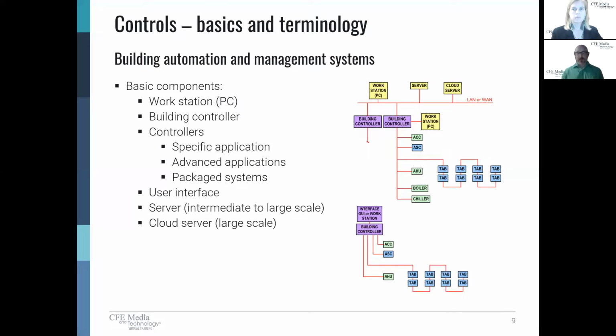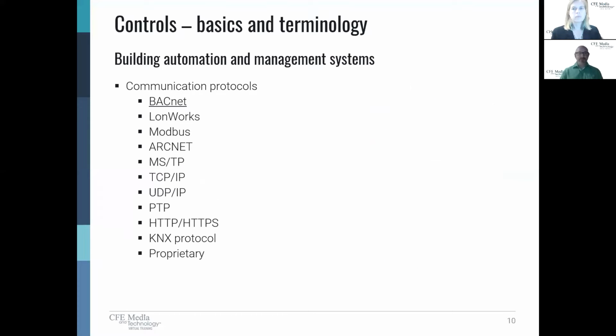Now, it's really important that engineers take this into consideration at the very beginning because it's going to affect the type of system that you're going to want to use. Now, there's a variety of ways that these building automation systems can communicate. BACnet is my personal favorite because I don't have to worry about the individual points. I can actually just say connect to the system via BACnet, and then all the information that the vendor provides is available for use. Now, another common system that we run into is Modbus.